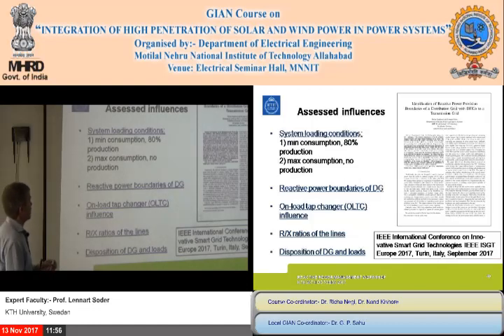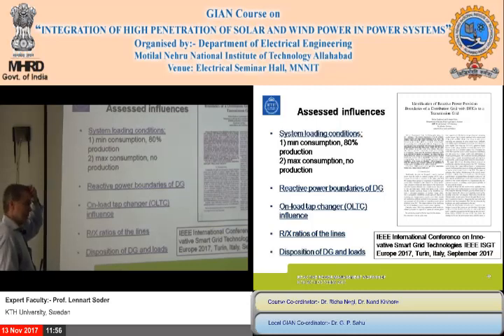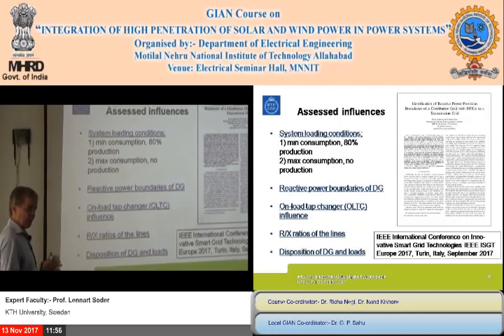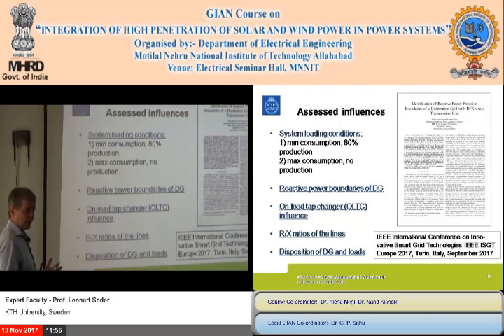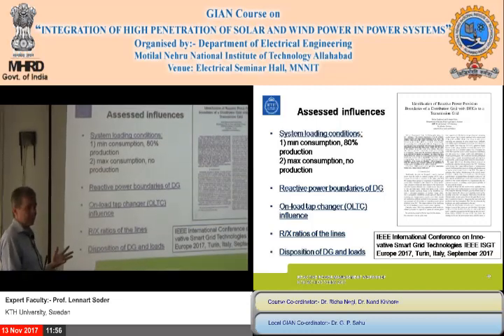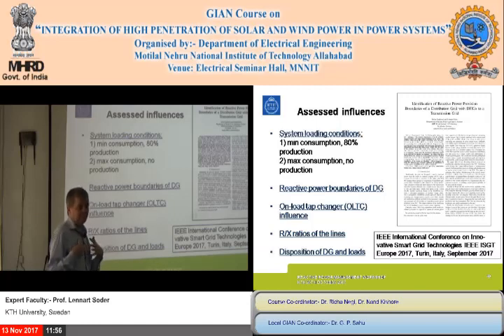This was a paper on identifying reactive power provision boundaries in a distribution grid. You get the same thing if you have solar power. The challenge is that the solar power converters — one of the basic assumptions here is that the converters can be used also when it's not windy. That is technically possible, but normally not the setting. For example, in my house, I have a converter that could technically produce or consume reactive power, but the setting is that in the night it's not connected, because then it's better to disconnect it so I don't create any losses.